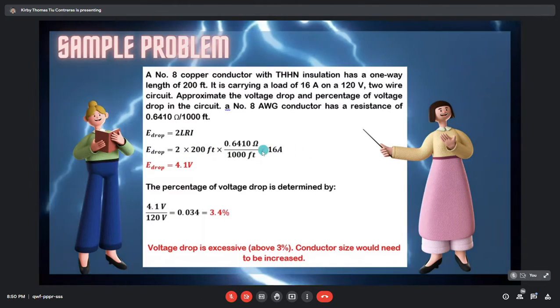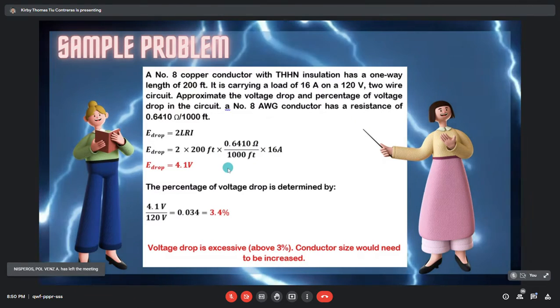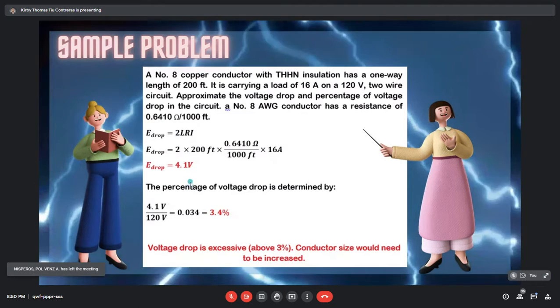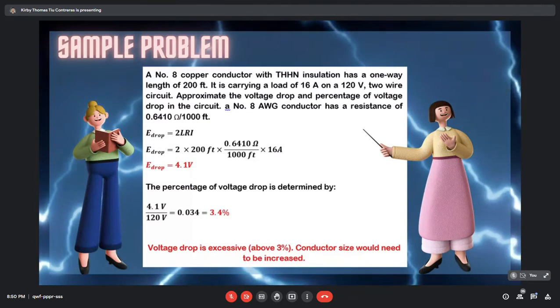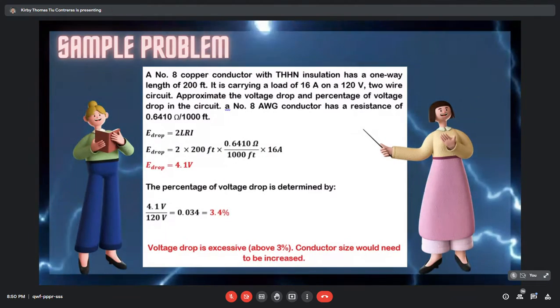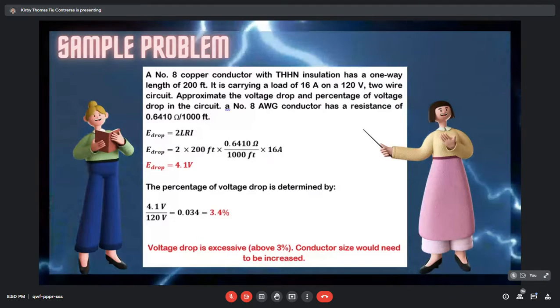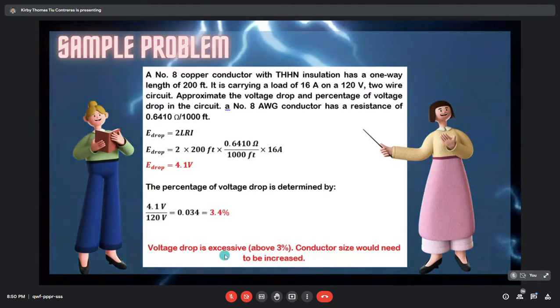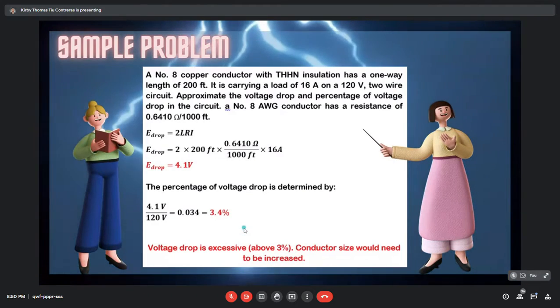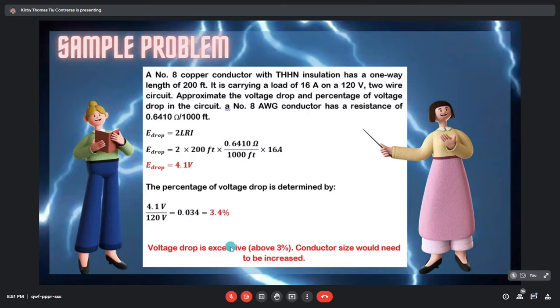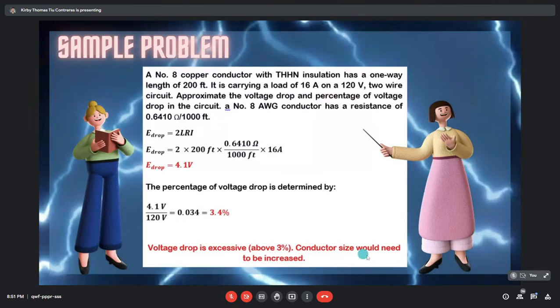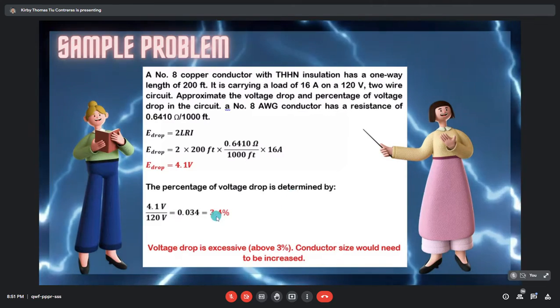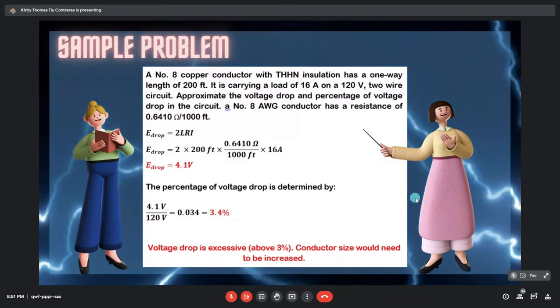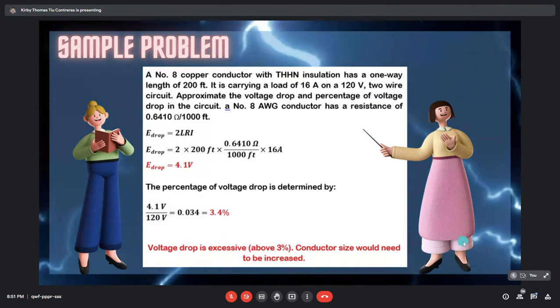So evaluating, we'll get a voltage drop of 4.1 volts. Then to get the percentage of voltage drop, we divide the voltage drop we got by the total voltage and multiply by 100%. Evaluating again, we have 3.5%. So here you go. Voltage drop is excessive above 3%. So the conductor size would need to be increased. Since it is 3.5%, we need to increase the size so that it will not overheat.